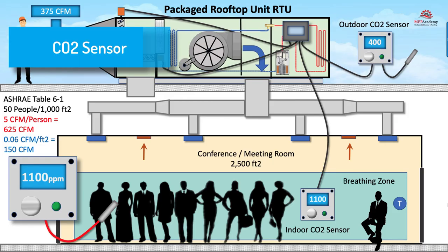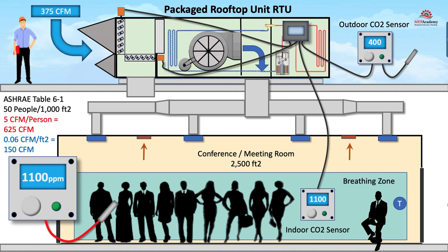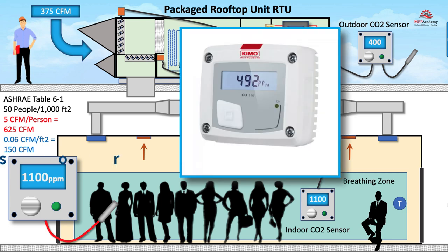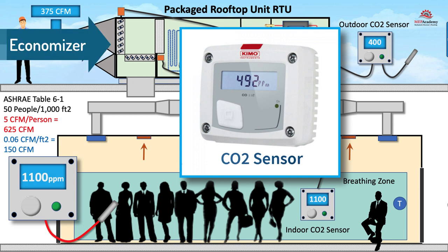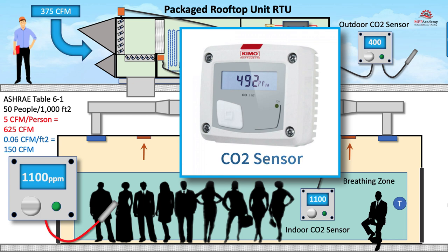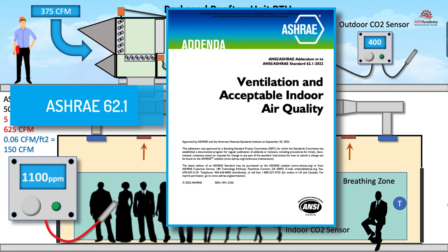CO2 sensors. Carbon dioxide CO2 sensors are used to monitor indoor air quality and ensure adequate ventilation. They are often placed in areas where people gather, such as conference rooms, classrooms, and auditoriums. CO2 sensors, when integrated with economizers, play a vital role in controlling ventilation air to a room based on the levels of CO2 present in the indoor environment. The CO2 sensor continuously measures the concentration of carbon dioxide in the air. Based on building codes and standards such as ASHRAE Standard 62.1, there are recommended or required ventilation rates for occupied spaces. These rates are designed to maintain healthy indoor air quality.